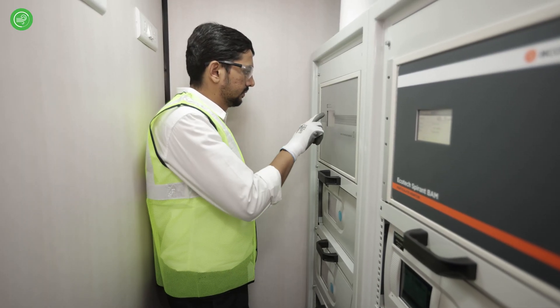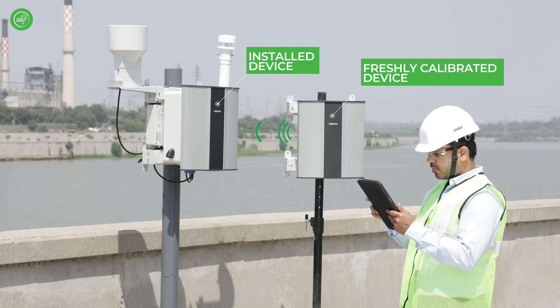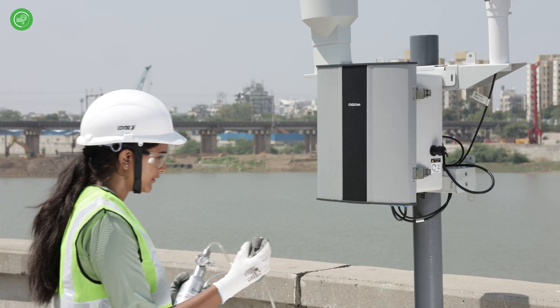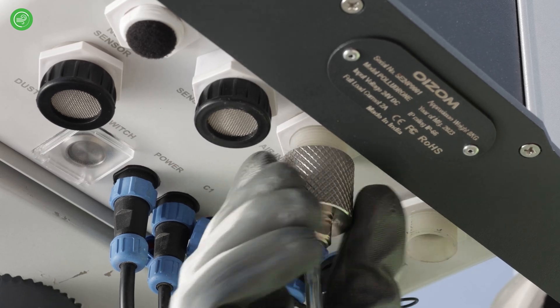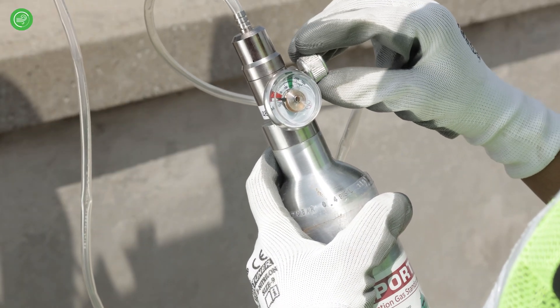The reference standard could take the form of a stationary reference station, a mobile instrument, or a freshly calibrated OIZOM unit. The active sampling design of OIZOM's air quality monitors provides users with the benefit of easy field calibration using portable gas cylinders or gas generators. The device can be calibrated on-site without the need for relocation by passing known concentration gases through the system using a custom calibration hood for up to 20 minutes.